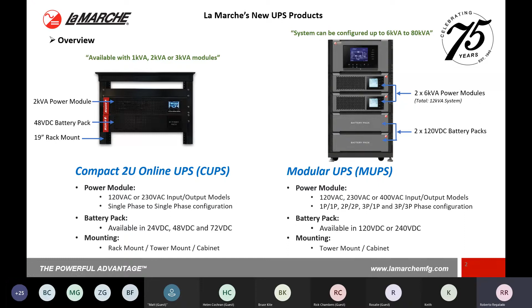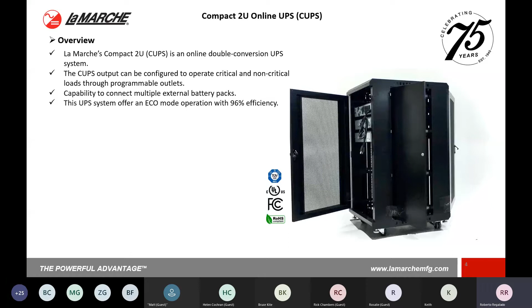Okay, now just to focus more on the modular UPS, here's a little bit more of a setup that we actually have done in the past. The cabinet that you see rotating there was configured for a specific customer where they only needed a specific number of power modules. They actually had battery racks there as well, but they also had an external battery pack that they could have added to it. So that's why you don't see anything too packed with modules, power modules, or battery packs. It is a double conversion UPS system, so it is your AC to DC and your DC to AC, and it's obviously configured for your critical and non-critical loads.